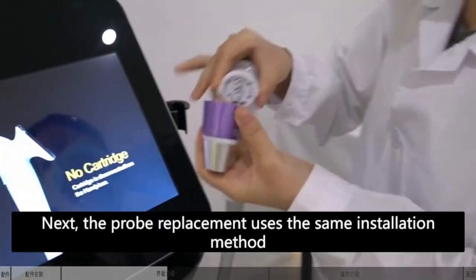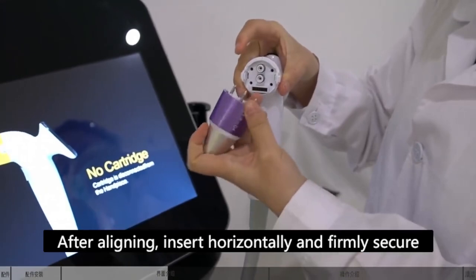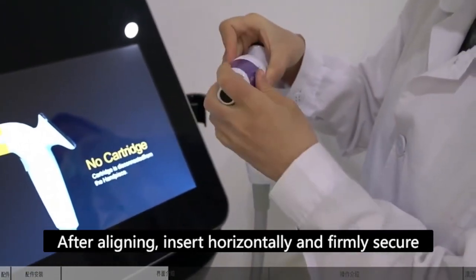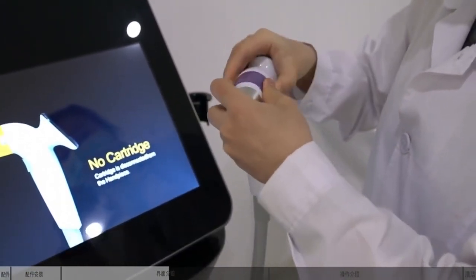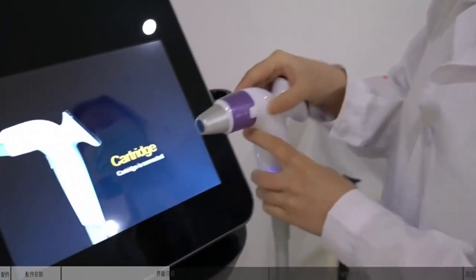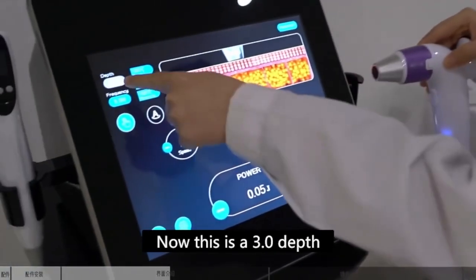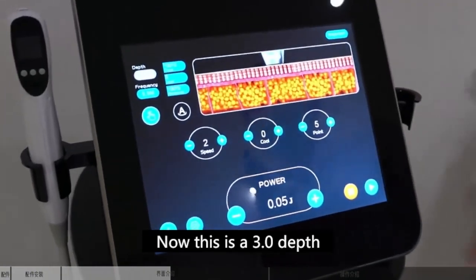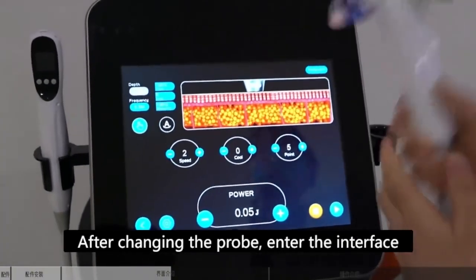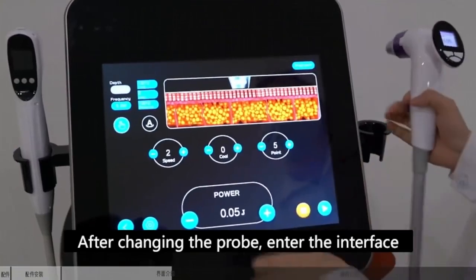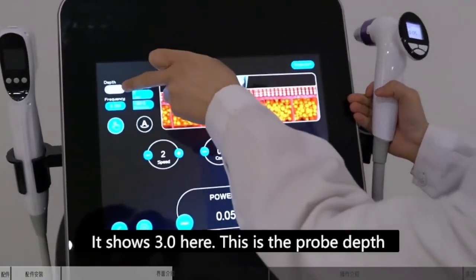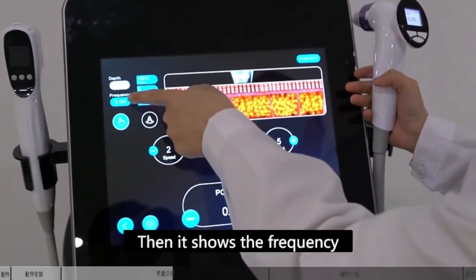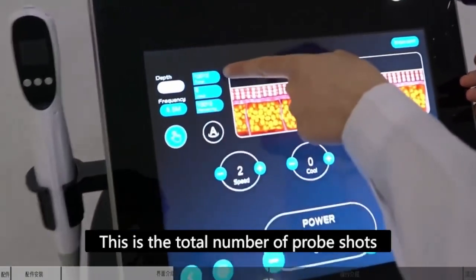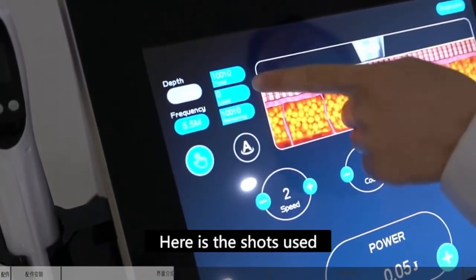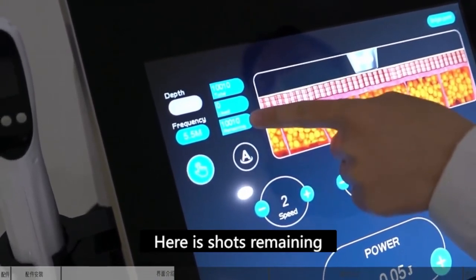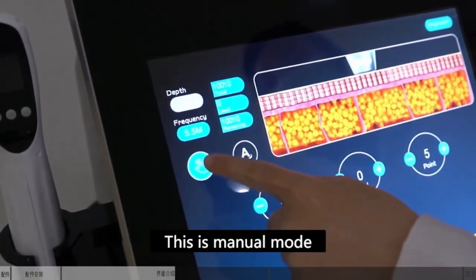Next, the probe replacement uses the same installation method. After aligning, insert horizontally and firmly secure. Then it will auto-sense. Now, this is a 3.0 depth. After changing the probe, enter the interface. It shows 3.0 here. This is the probe depth. Then it shows the frequency. This is the total number of probe shots. Here is the shots used. Here's shots remaining. This is manual mode.